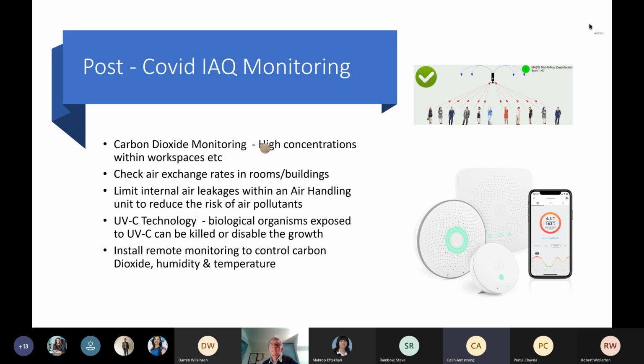You can use HEPA filters. However, if you put a HEPA filter in, there'll be a high pressure drop and you'll need potential modifications, and it's not always an option to fit HEPA filters onto an existing system. Alternatively, you can install a disinfectant device into an air handling unit. You can put an ultraviolet germicidal irradiation device in there, and that will kill it off, but it's essential that it's correctly sized and installed. If technically possible, it's preferred to mount a high-class filter in the existing frames and to increase the exhaust fan pressure without reducing the airflow rate.